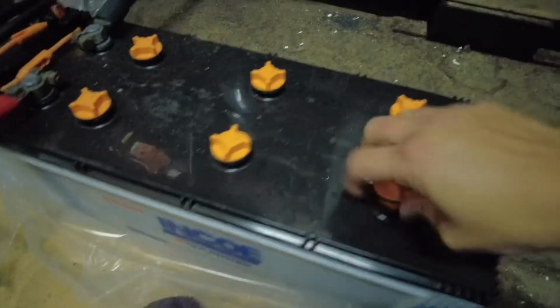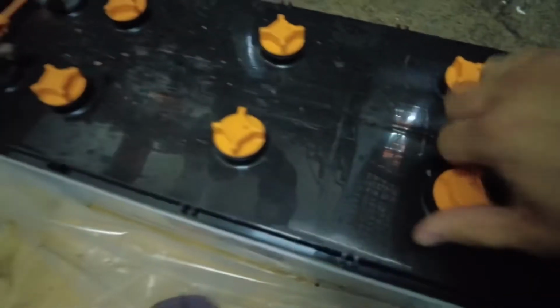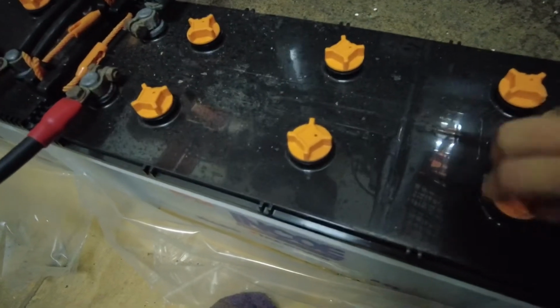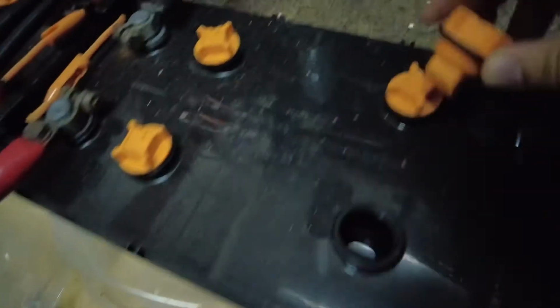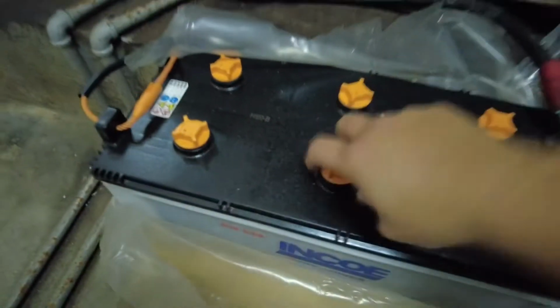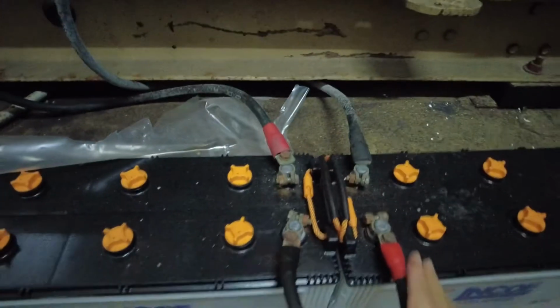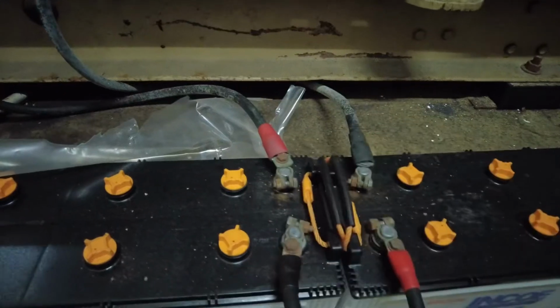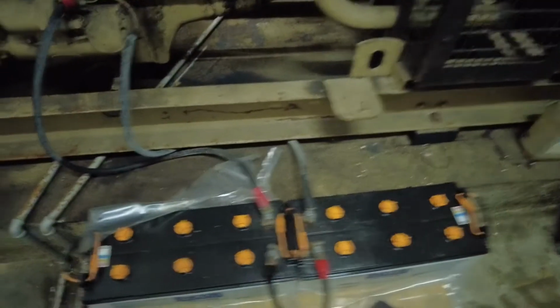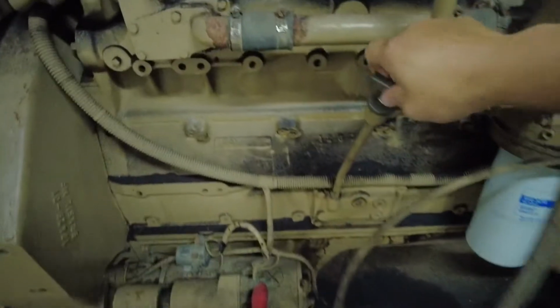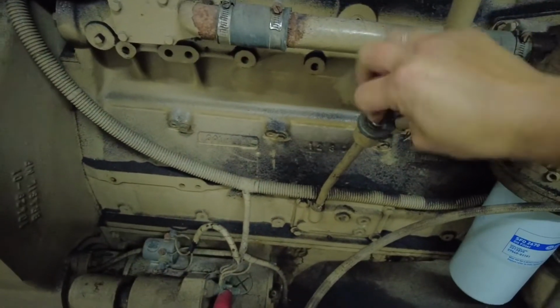First of all, let us have a look at the battery. Make sure the water is sufficient. If not, need to fill up. They're using the lead acid battery, which is a lorry type. 12 volt and 12 volt here. Series connection, it become a 24 volt DC. Check that the cable is tightened, no loose. Alright, and let's check the engine oil.